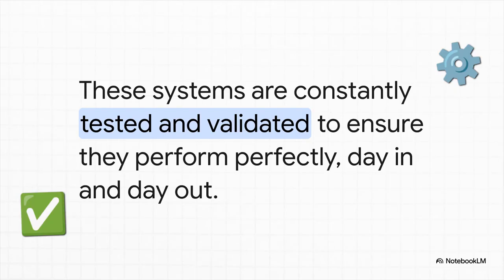And you can't just set the stuff up and walk away. It's not a set it and forget it kind of thing. A clean room is really like a living, breathing system. It has to be tested and revalidated constantly. Technicians are always in there with particle counters and doing smoke studies to prove with cold, hard data that the system is working perfectly every single day. There is absolutely zero room for error.